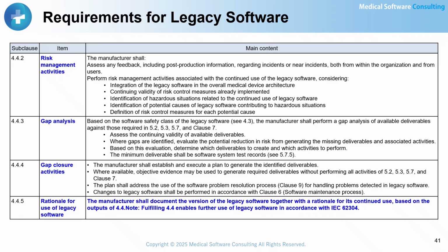legacy software into the overall medical device architecture, continuing validity of risk control measures implemented within the legacy software, identification of hazardous situations that could arise from its continued use, identification of potential causes where legacy software could contribute to hazardous situations. Definition of risk control measures for each identified potential cause.